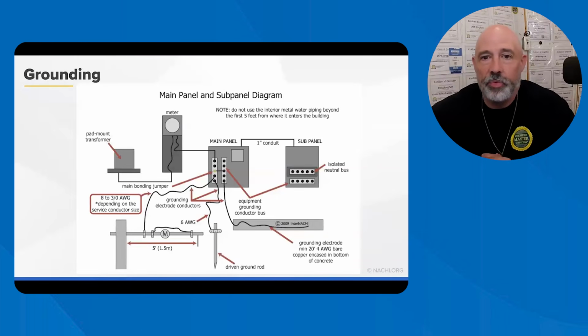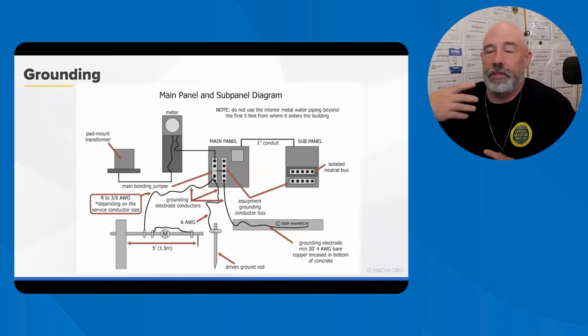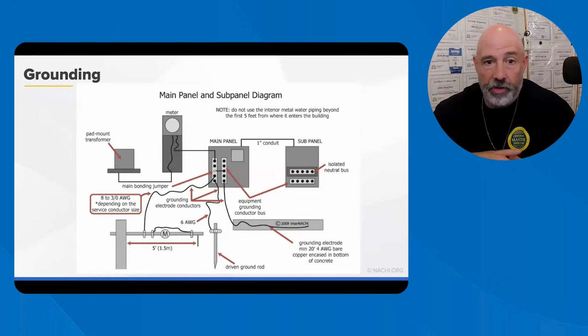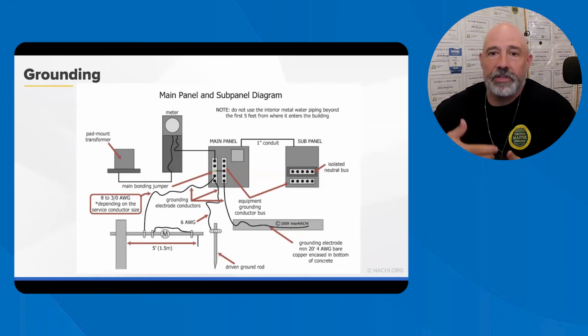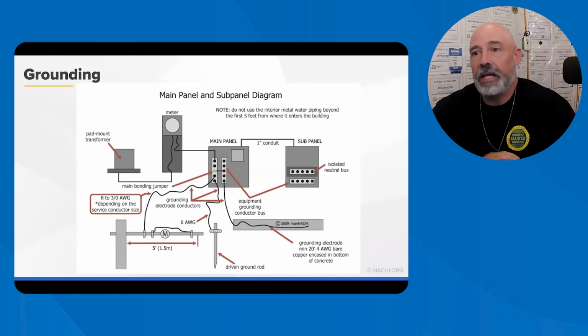Grounding and bonding. This is one of the most confusing topics, and that's why I did the Electricity 101 grounding and bonding course, or sorry, the webinar. Grounding connects the electrical system to the earth. It helps dissipate lightning strikes and voltage surges. Bonding connects metal components together to provide a safe path for the fault current and helps breakers trip quicker during that fault.